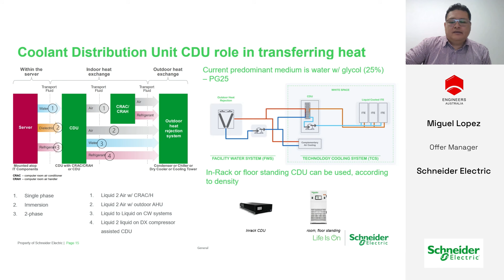So what are some of these liquid cooling architectures? Essentially, you have here a graphic of what the CDU is doing. The inbuilt pump of the CDU is essentially recirculating the water to and from the IT equipment. And as you can see there, the returning warm water is then fed through a liquid-to-liquid heat exchanger. That heat exchanger then is removing that heat back to an outdoor heat rejection system. Could be a chiller, a dry cooler, etc. The outdoor system will have its own pump that will be recirculating that fluid.